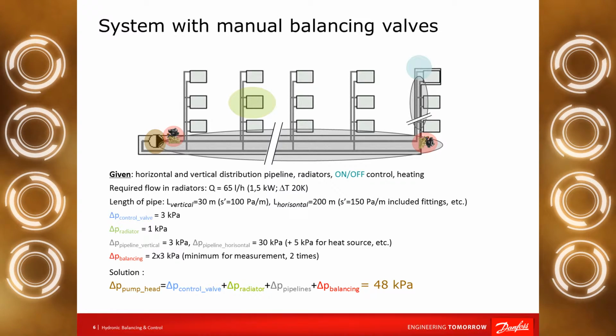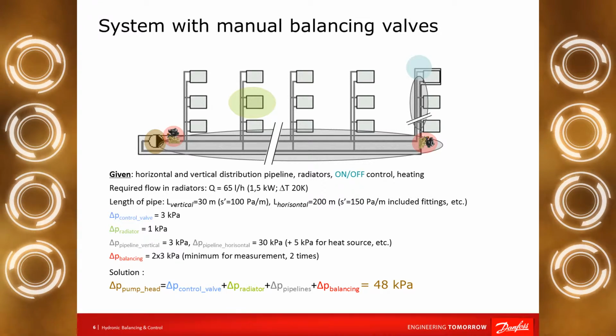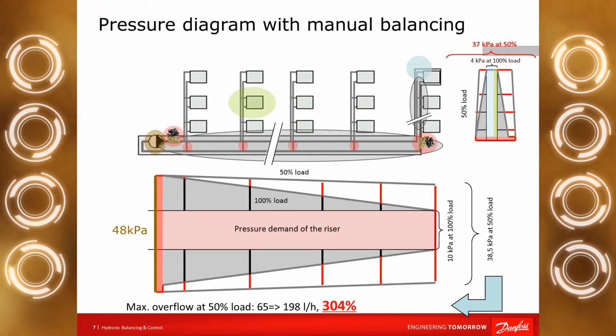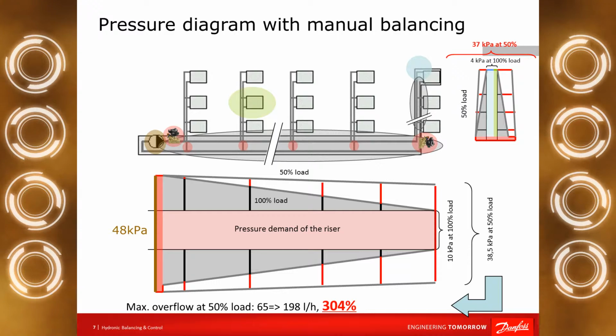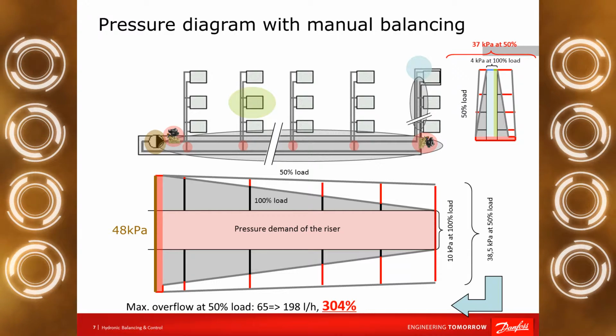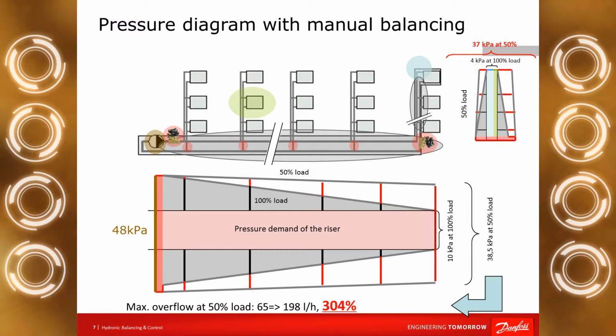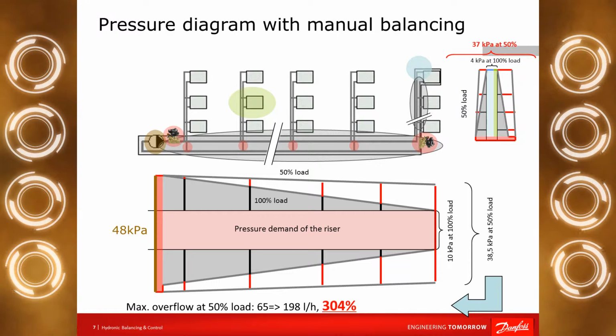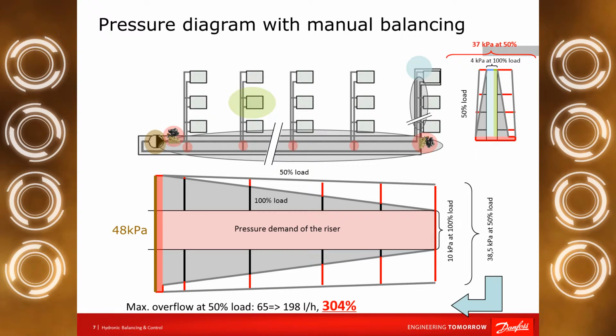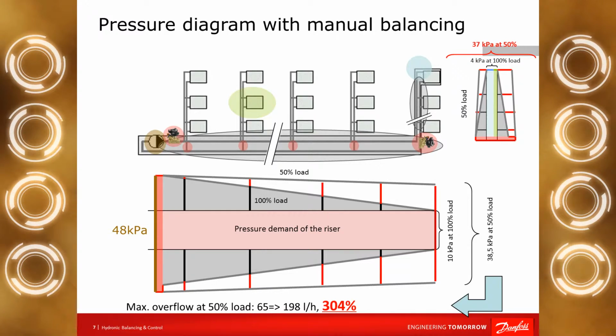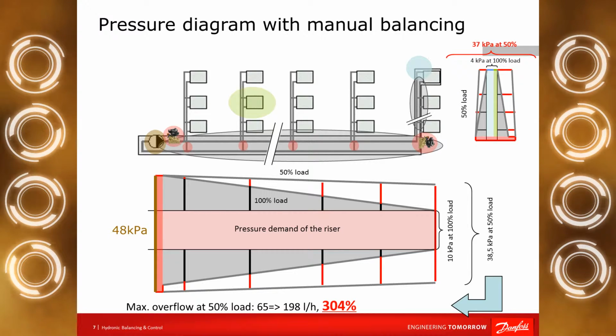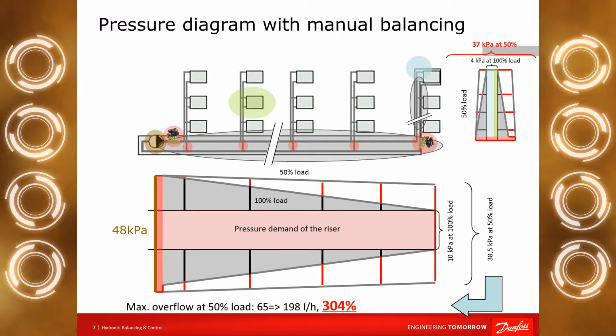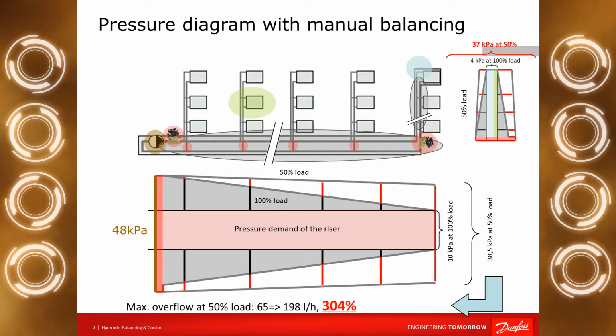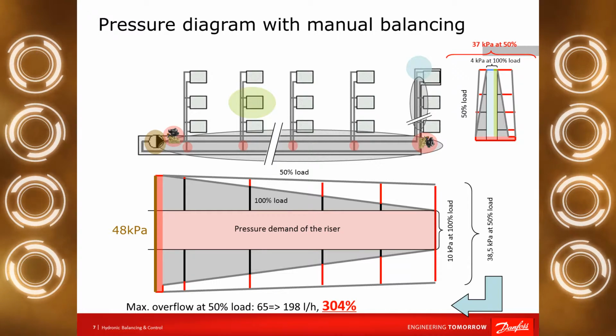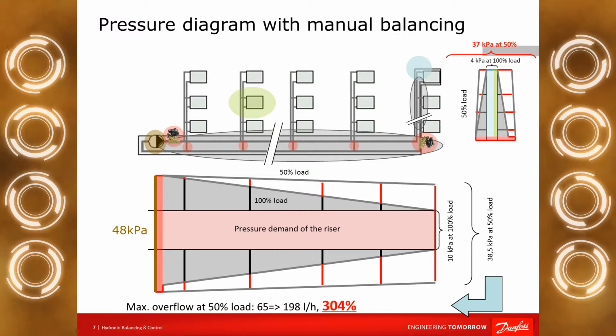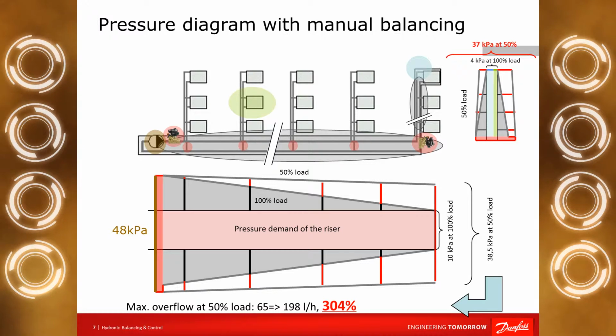This is the engineering. But we cannot stop at that point, because we have to know the pressure diagram of our system. Let's see what the real pressure graph is. We have the riser, and the pressure demand of the riser's radiator control valve, and in gray you can see the extra pressure demand for the pipe pressure drop. At the bottom of the riser, you can see a pink area. This is the pressure demand of the manual balancing valve at the bottom of the riser. We have to ensure this minimum delta P for the riser at the bottom of all risers. The distribution pipeline pressure drop we also have to add to the total picture. And now, with the extra manual balancing valve in front of the pump, we see the pump head demand.